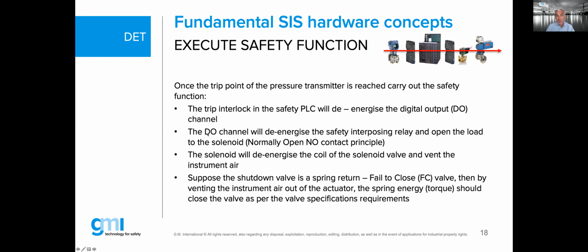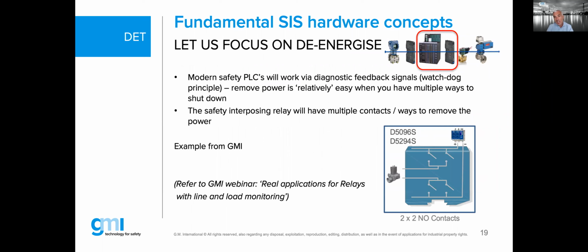Typically, a digital output channel will de-energize the output and will try to open the contact of your interposing relay over here. And then that interposing relay on its own will try to remove the power here of the final element. First of all the solenoid, and the solenoid will try to vent the air of the actuator of the final element. That's all normal practice. I don't think I have to explain more about this. Let's go a little bit more in depth, and let's start here with the interlock. The interlock itself will be some application program written in a modern safety PLC.